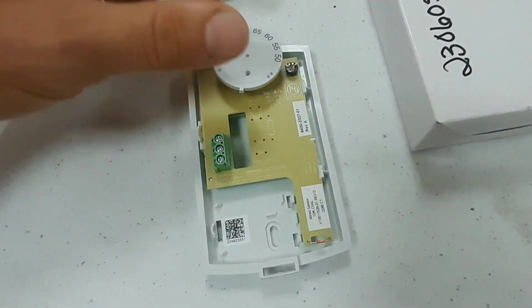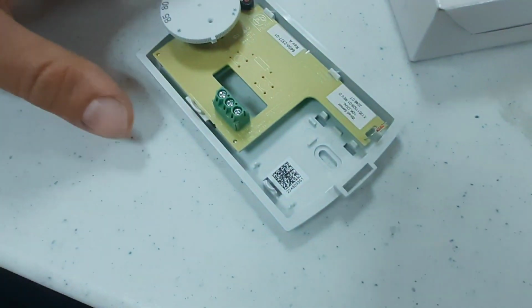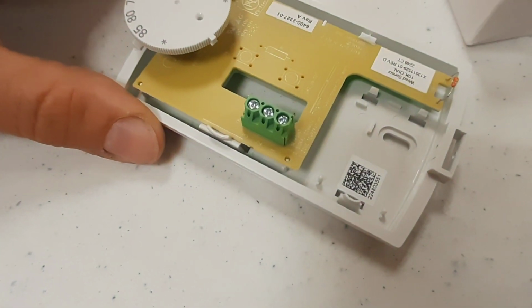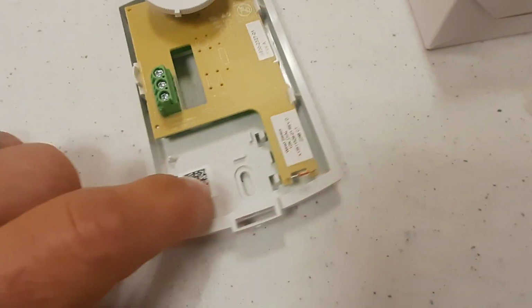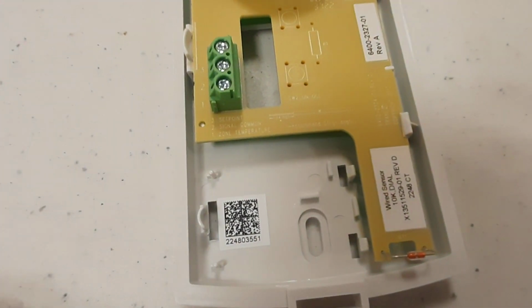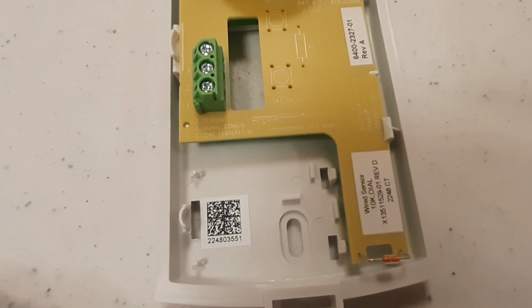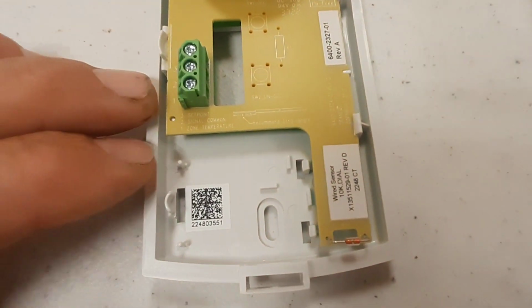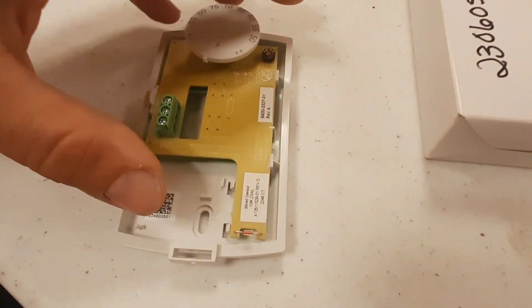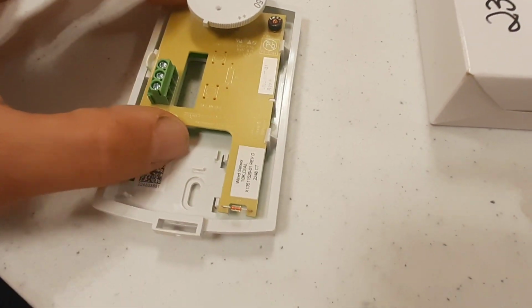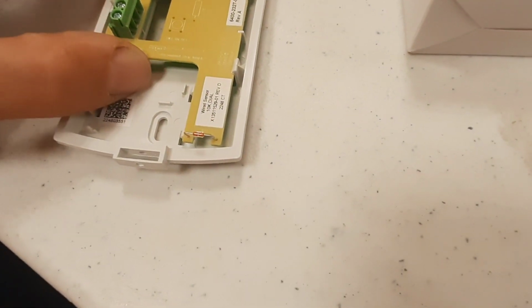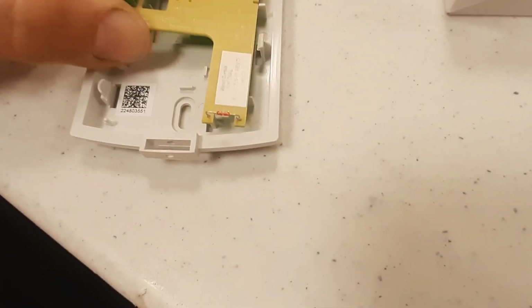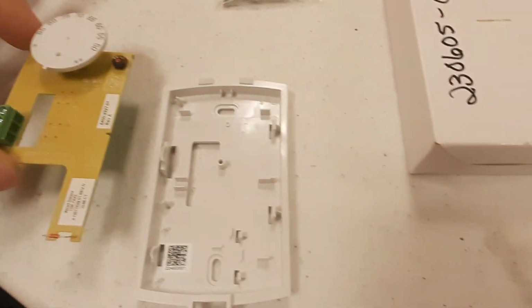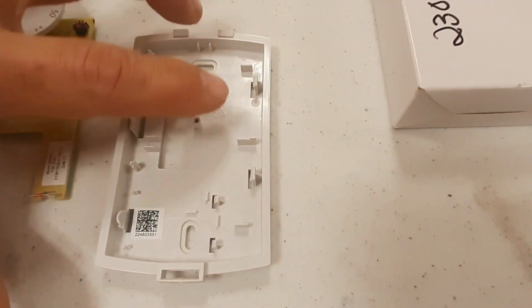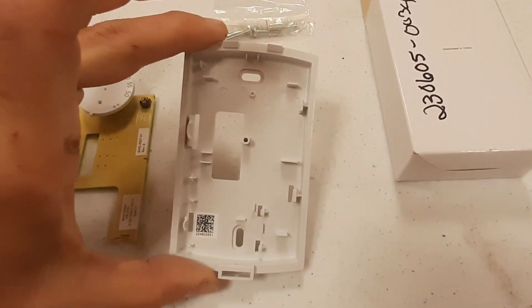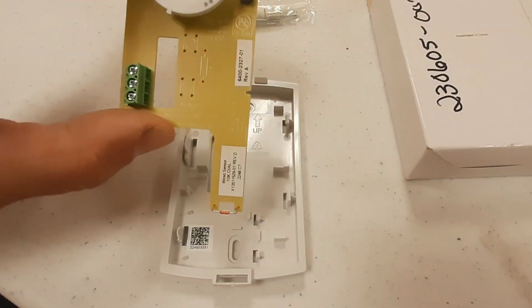Now with these sensors, this is your thumb wheel sensor here. It's not real complicated. 1, 2, and 3. It's gonna be zone, ground, and set, and it actually says it there on the bottom. Zone temperature, signal common, and set point. 1, 2, and 3 is gonna match up the same way on the VAV box, same numbers. This circuit board, this is your temp sensor. This board will actually come out of here, like so. Pops in 3 spots, and we can mount that guy and pop the board back in.